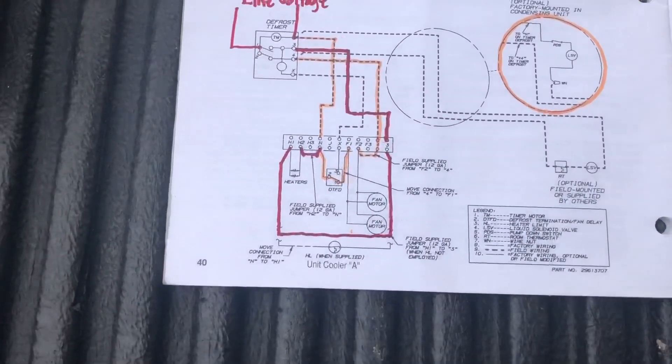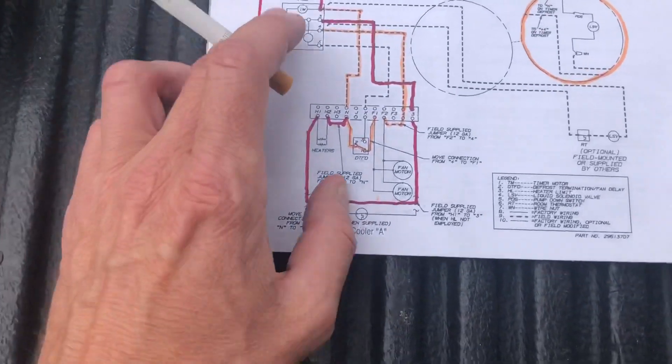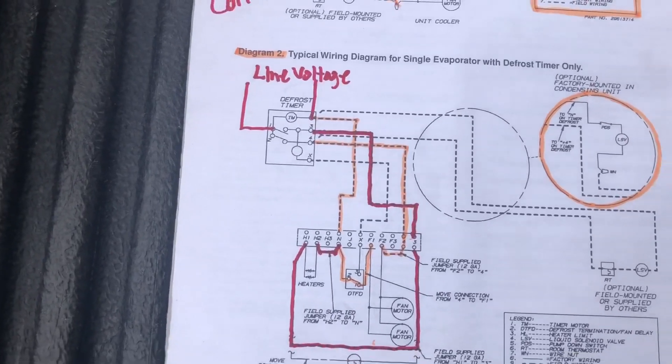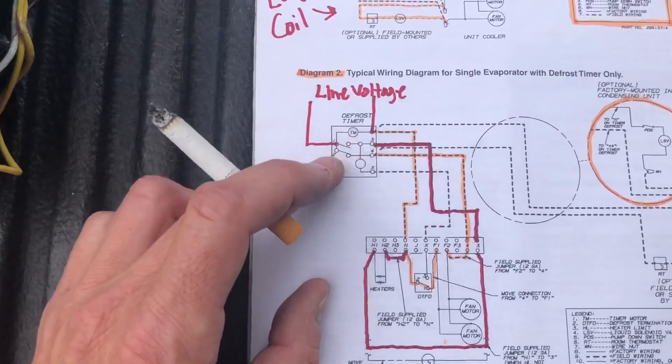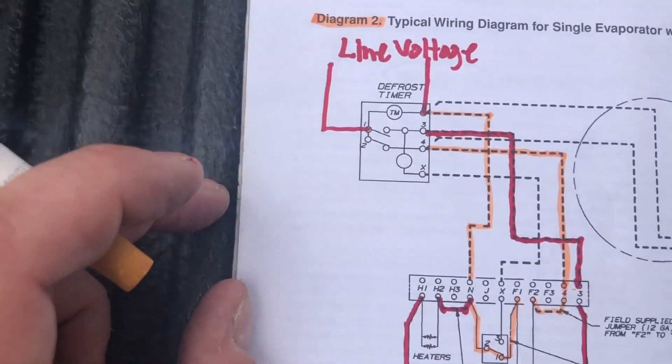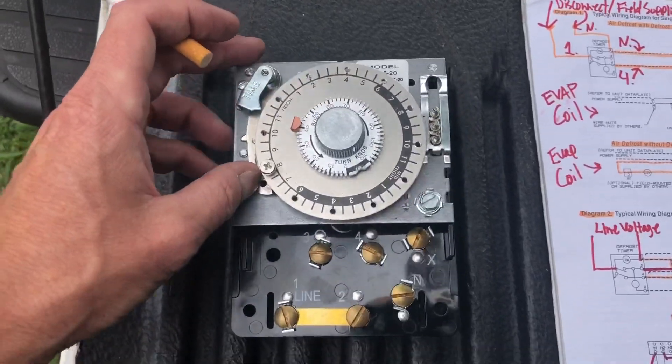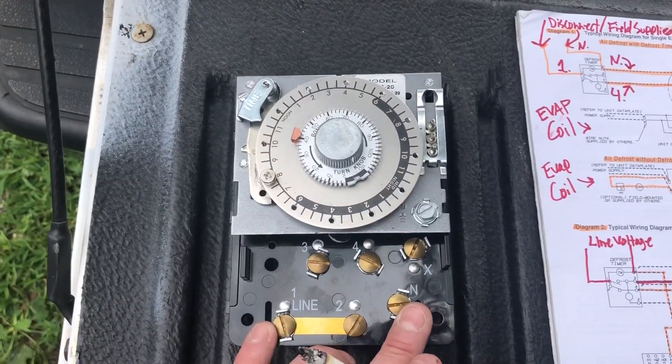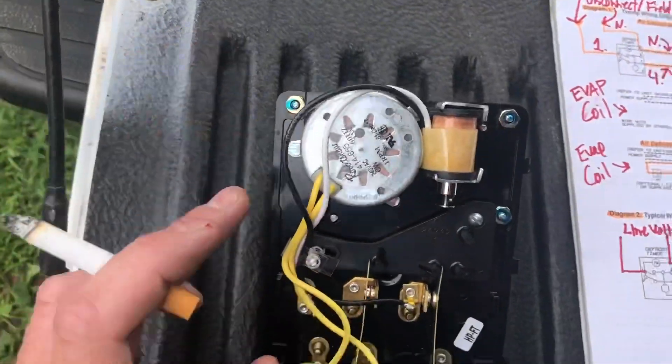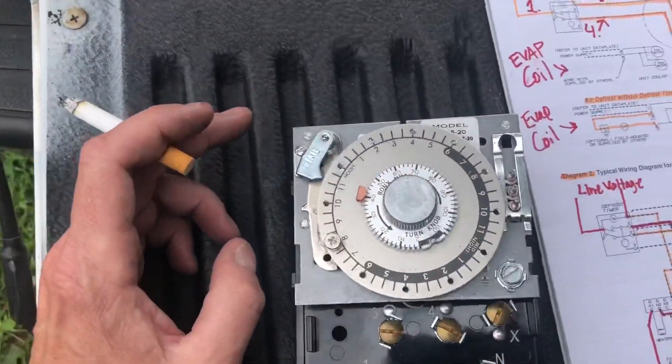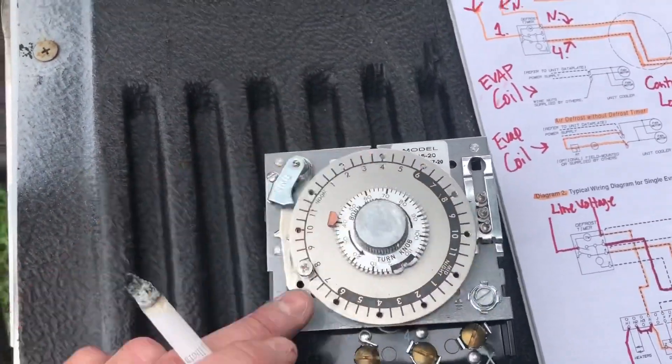How we're gonna start is we have our line voltage coming in. We're gonna go with this being a 208-230 volt system. We have our line voltage coming in which is always going to power our timer motor on 1 and N, which is here. Here's your basic Paragon clock, this is 8145-20. So we got 1 and N with our lines coming to it. They are going to be powering this right here, our timer motor, which runs 24/7 every day. And that's what spins around, and when it hits one of these pins over here it clicks into our defrost cycle.